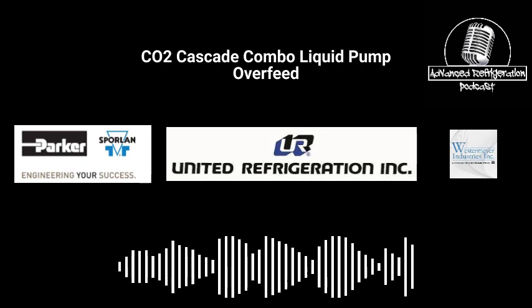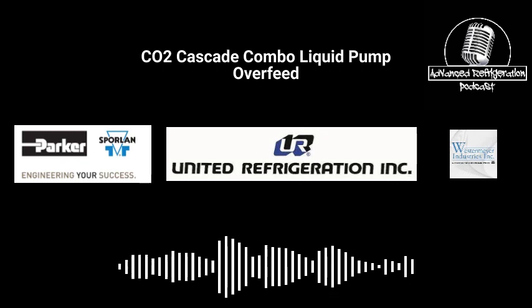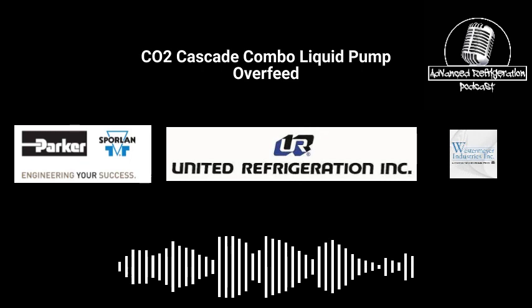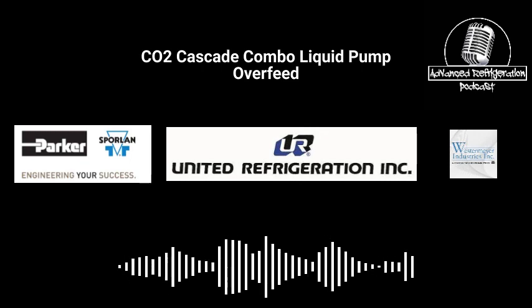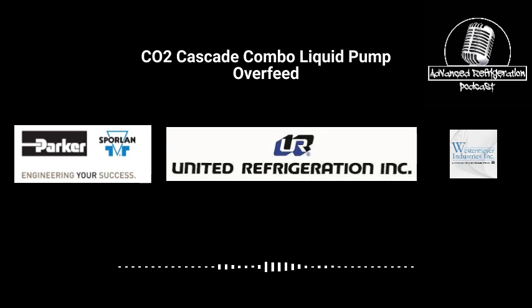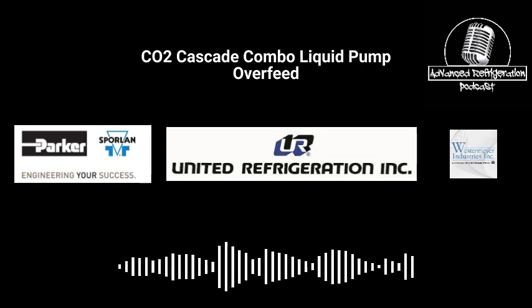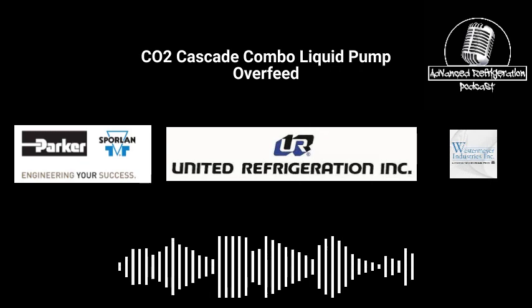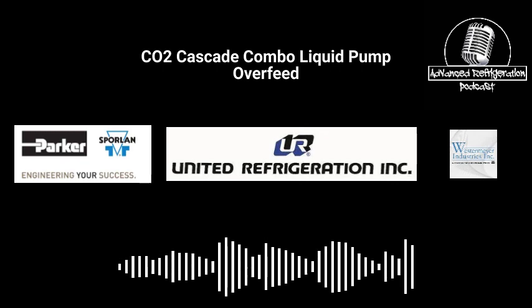The other part of it is they're installing these racks more in areas where transcritical is going to cost more to run. So this all comes down to a cost aggregation, whether it's cheaper to run a cascade rack or a transcritical rack. It really depends on where you are. Like, I'm up north, transcritical beats a cascade all day long.